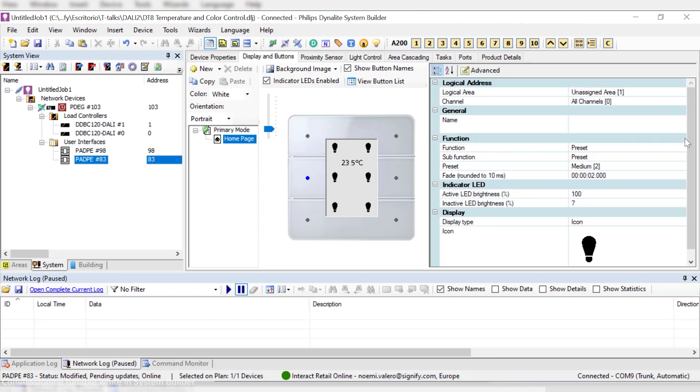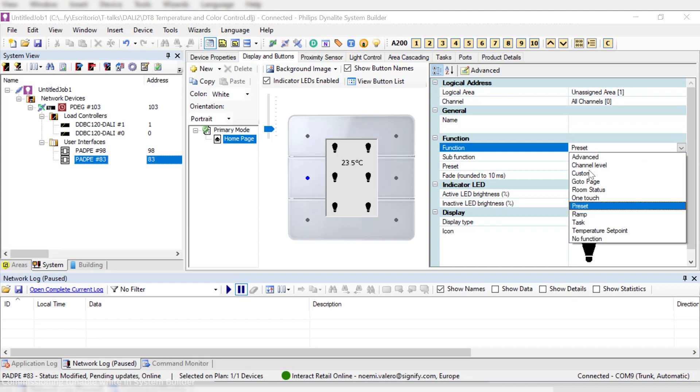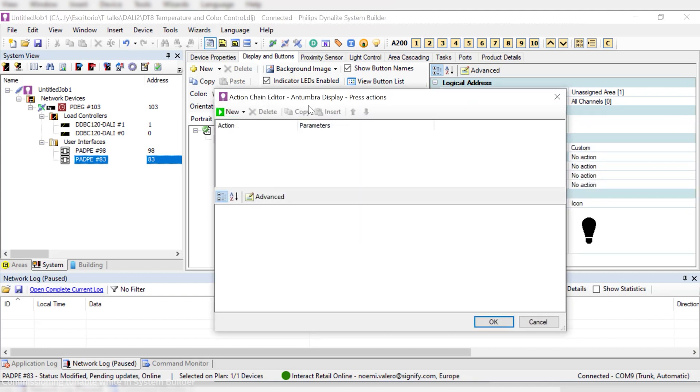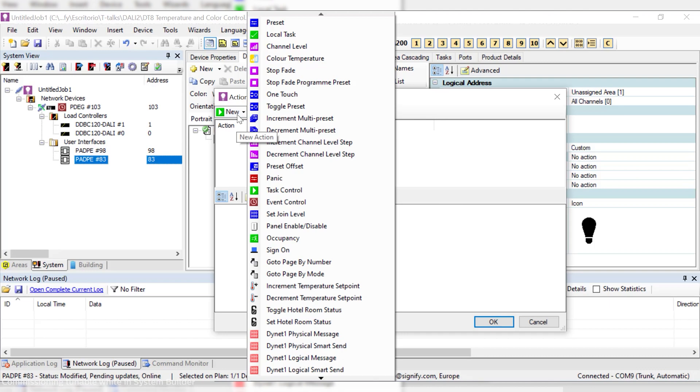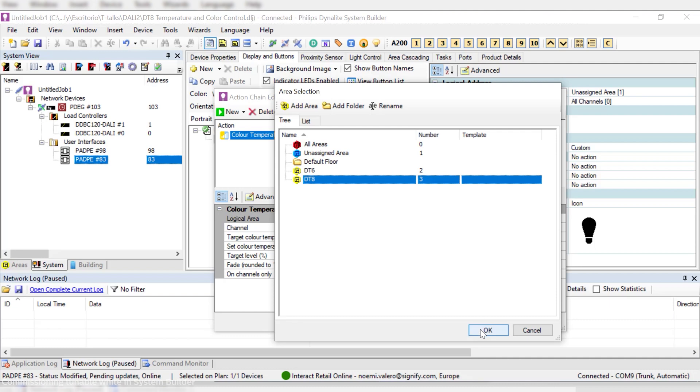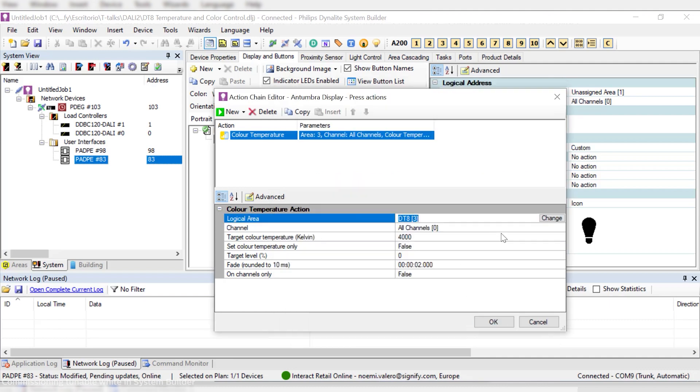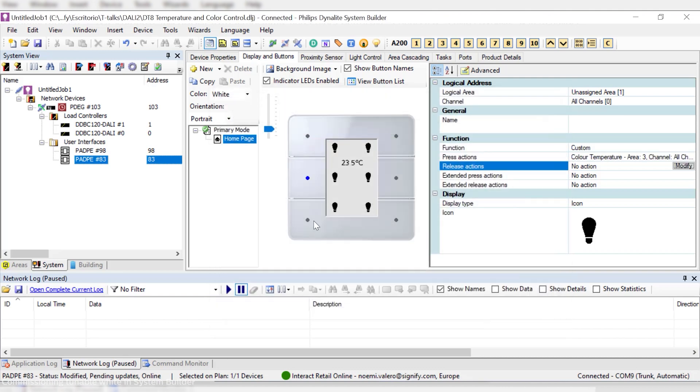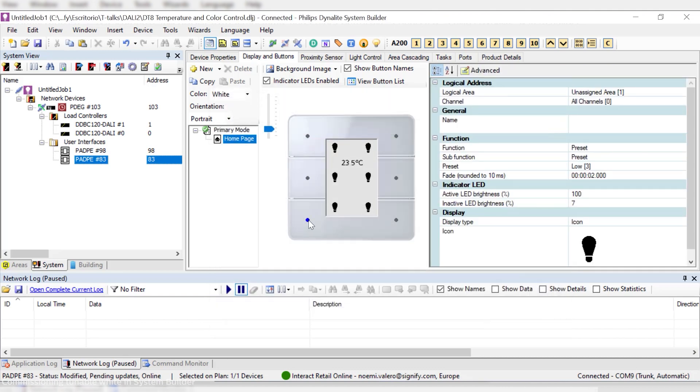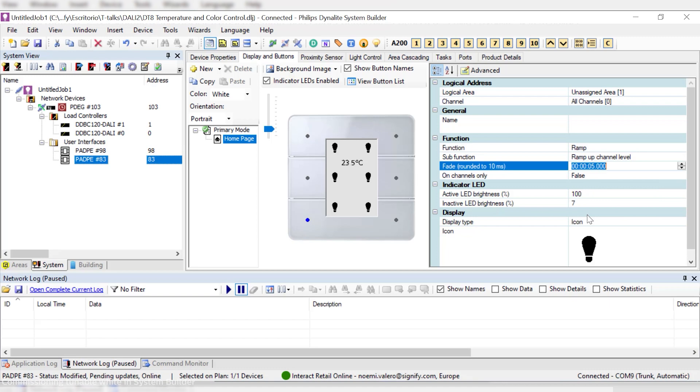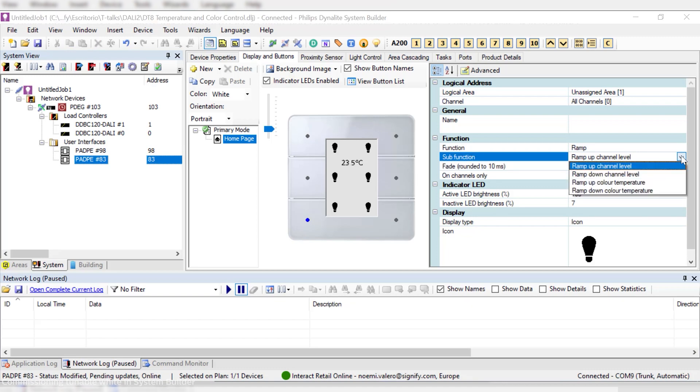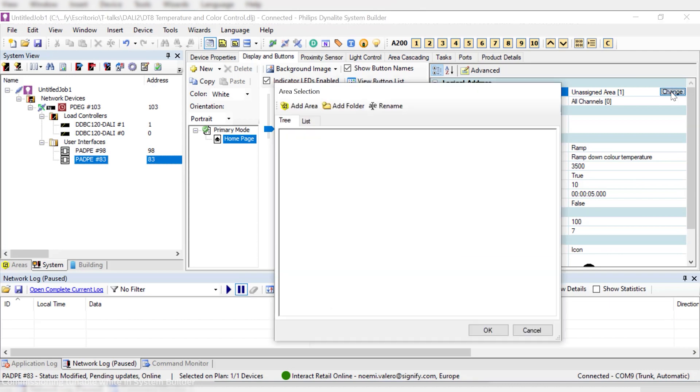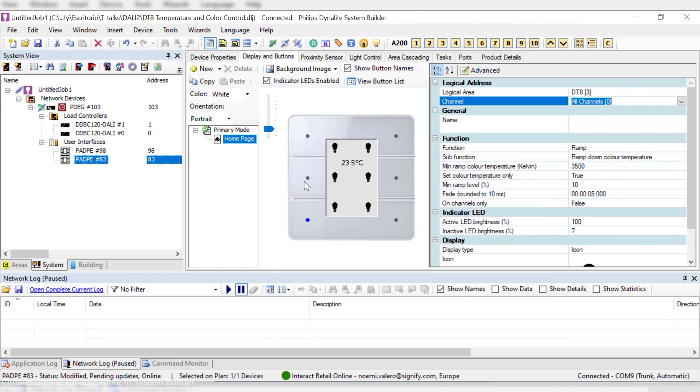In the next button, we can program a custom behavior. This will require to open the Action Chain Editor and select a Color Temperature command. We will define the area, in this case our DT8 area, the color temperature that can preferably be 4000, and the light output, let's say 50%. For the last two buttons, we'll use the Color Temperature ramp to let the user have more power to balance between cool and warm white. First, we will create the ramp down by selecting it from the menu. We will be able to limit the minimum color temperature, for example, to 3500 Kelvin, and the minimum channel level, which in this case is 10%. Remember to select the area where you want to apply these settings.